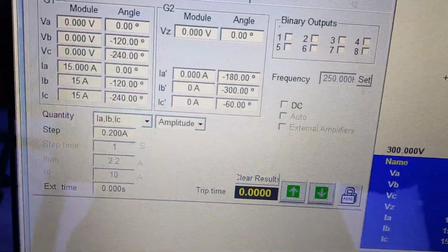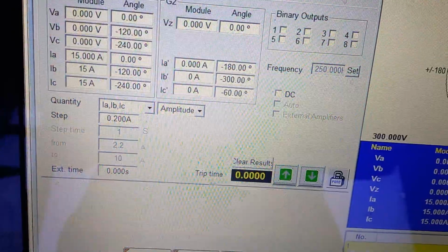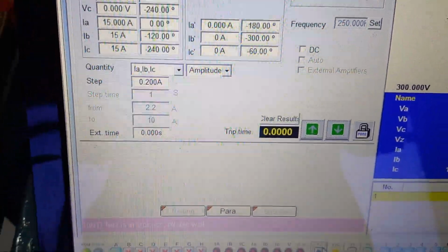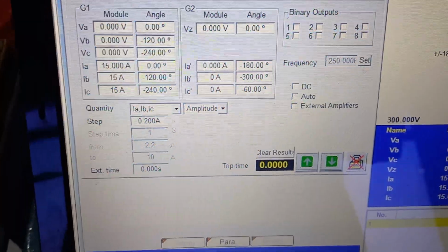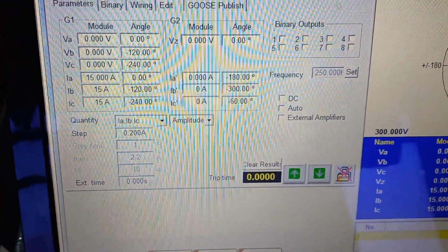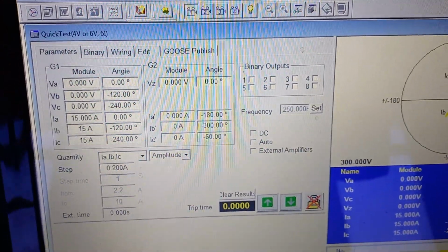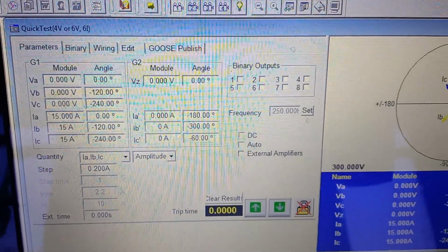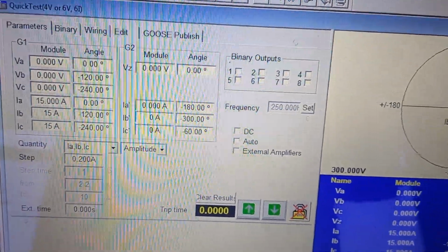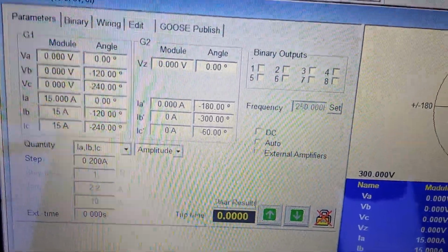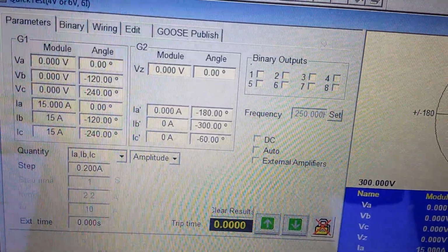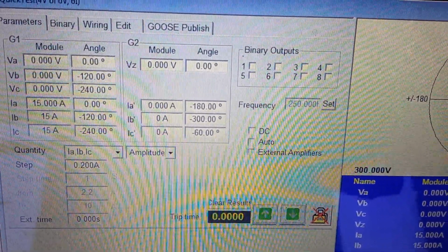Similarly, for the HS2 test, you just inject 15 ampere as per the relay setting and check in the LED and inside the relay whether HS2 comes or not. It should trip on HS2. It will not go to bias because this is the high set value, and the threshold limit is more than the insulation level of the CT or transformer, to protect the transformer. So when the value reaches this limit, it should not check any slope or any differential current. It trips immediately in the high set region.